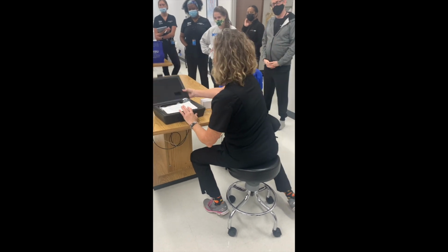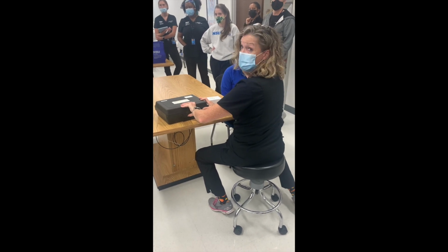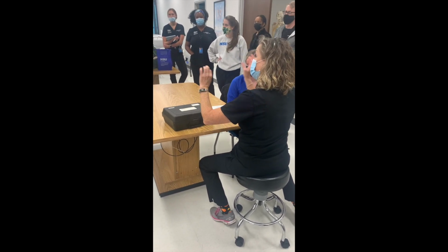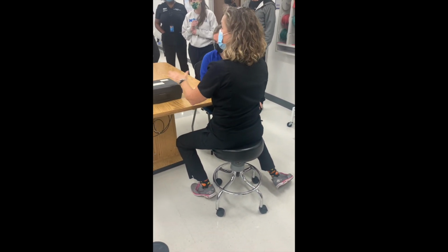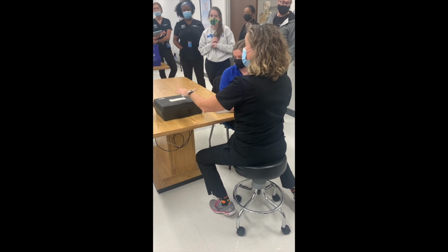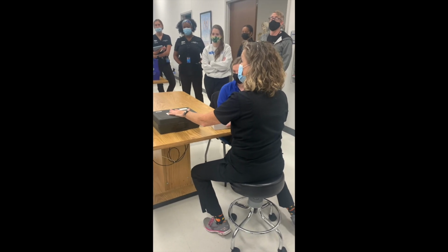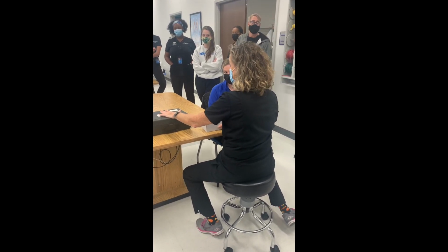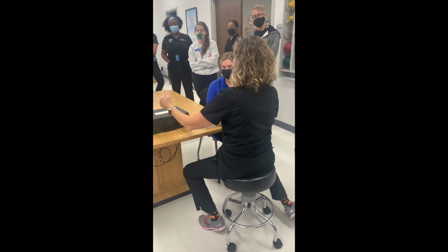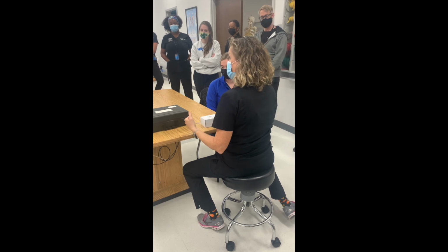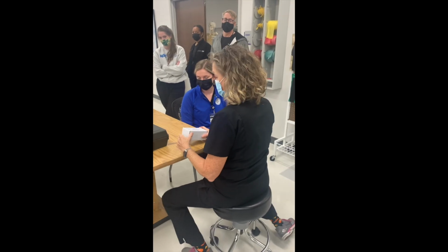These have to be calibrated every year. We're not using that today. When you're doing your measurement for opposition, you guys can come up here and use these. These have just recently been calibrated. They are very expensive instruments. Do not drop them. Do not bump them. If you do, you're going to pay for them. It took me a long time to get these calibrated. It was $1,800 for all of them. So it's not cheap. And anytime that you drop it or you hit it on the table, it can throw it off. So be very, very careful with them.